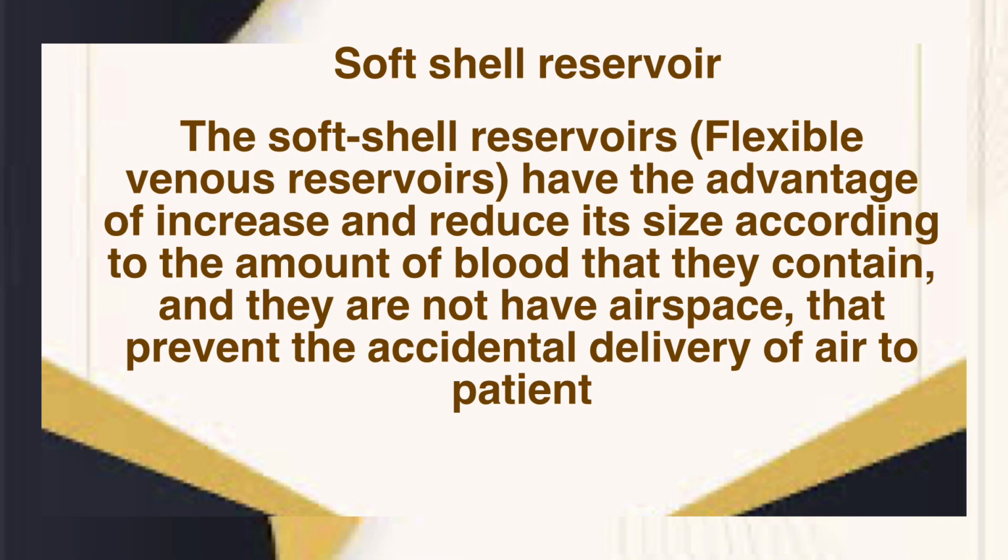Soft shell reservoir. The soft shell reservoirs have the advantage of increasing and reducing their size according to the amount of blood they contain, and they do not have an airspace, which prevents the accidental delivery of air to the patient.